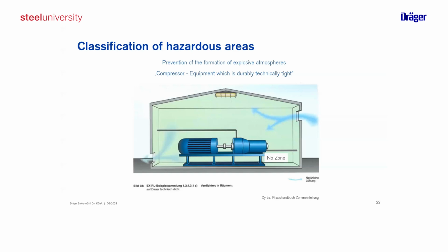Nice to know, or a nice effect, is if your resulting zone is no zone, you don't need to use, for example, a drive which is explosion protected, or light which is explosion protected, because as your design of measures always secures that no explosive atmosphere can build up, there is no necessity to select Ex-certified equipment. So it's a very interesting collection of different typical installations in the industry, and of the impact the measures have on the resulting zone.